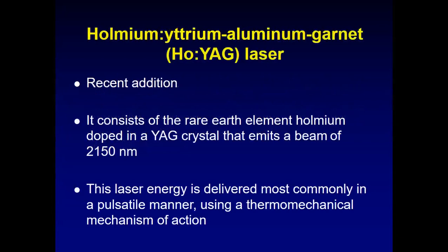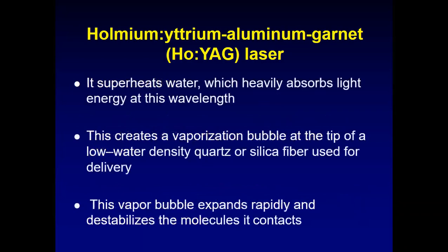This is the most important for urologists, the holmium YAG laser. It is a recent addition. I told you that few people say it has a wavelength of 2100 and few people say it has a wavelength of 2150. So it depends. YAG is the crystal, holmium is placed over it, and the laser energy is delivered most commonly in a pulsatile manner using a thermomechanical mechanism of action.